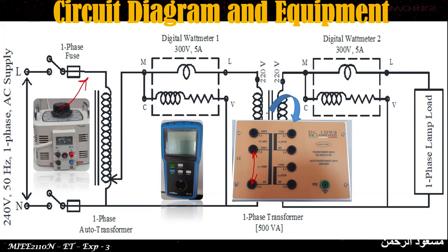And in the secondary side, the transformer we are going to use in this exercise is 220 by 220. It means the primary voltage is 220 volt and the secondary voltage is also 220 volt. But in the physical transformer, you can see two individual coils with 110 volt voltage rating. There are 2 secondary coils, individual secondary coils, each rated for 110 volt. We are going to connect these 2 coils in series so that the voltage will be added, the winding will become additive.